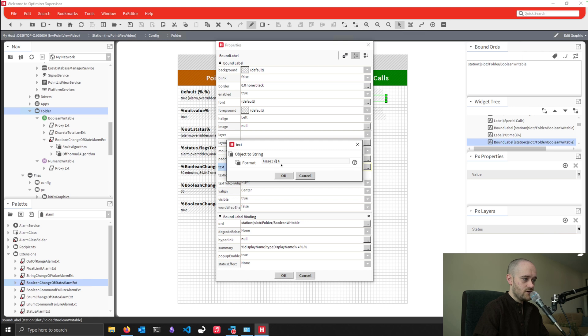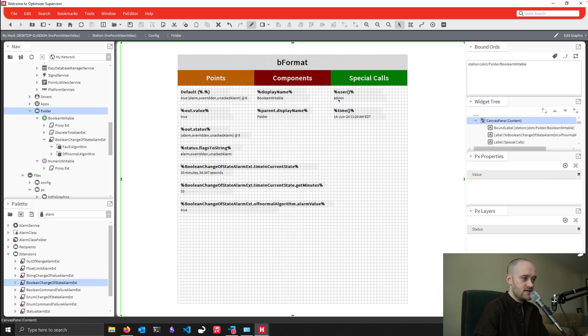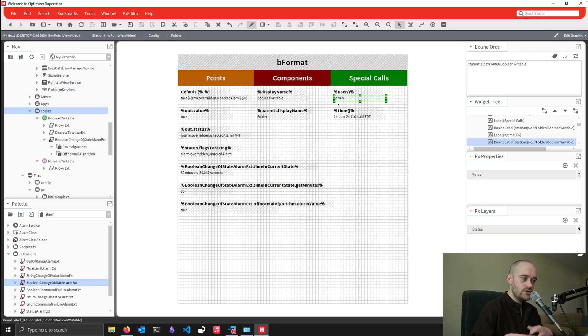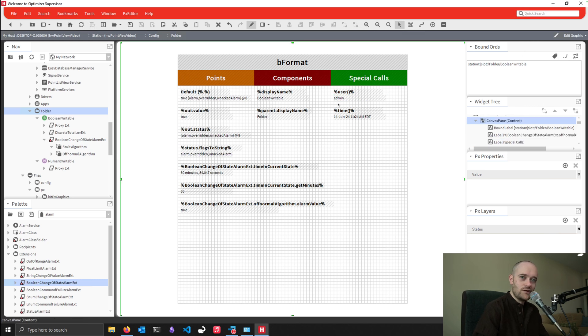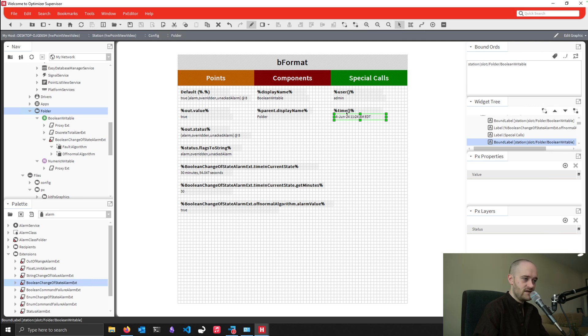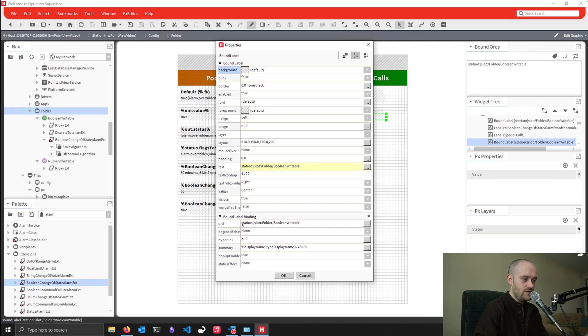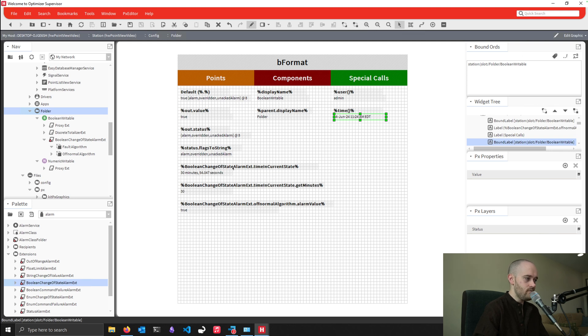There are also some special options. Even though my binding on this label is still the boolean writable point, I can call the user special method and it gives me the current logged-in user's name. This is helpful on graphics for headers showing who is currently logged in. Similarly, I can pull up the time using the time call, along with the various methods that are part of the time object — it doesn't matter what the binding is.